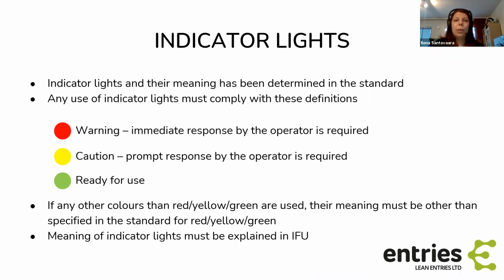One thing to note about the standard is that in the chapter about labels and information and things like that, it also gives requirements for indicator lights. So if you are going to use any indicator lights, then do note that these have been determined in the standard. So if you use any lights, indicator lights, you must comply with these definitions. So if you have a red light, that's always a warning, and immediate response by operator is required. And if you have a yellow light, it's caution, prompt response by the operator is required. And green light is ready for use.